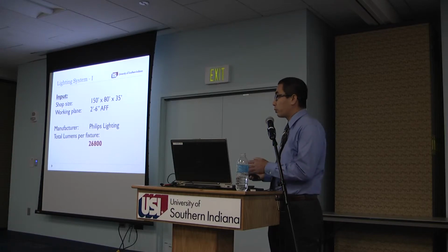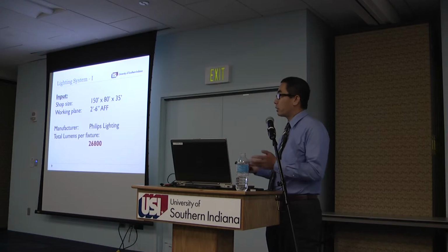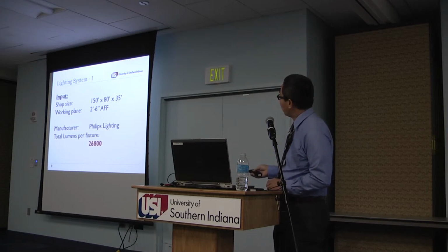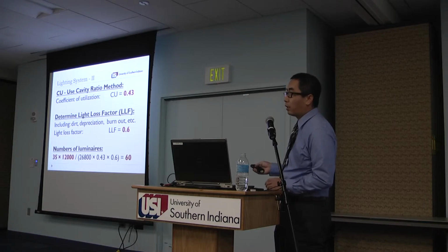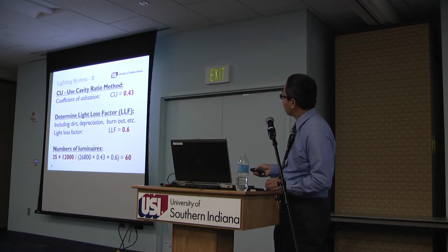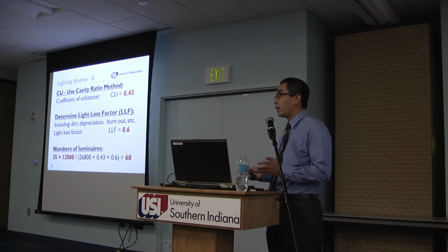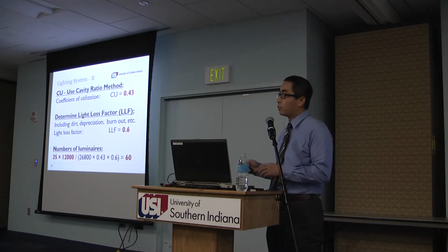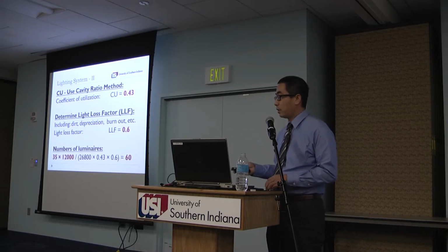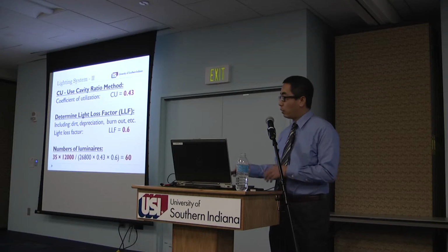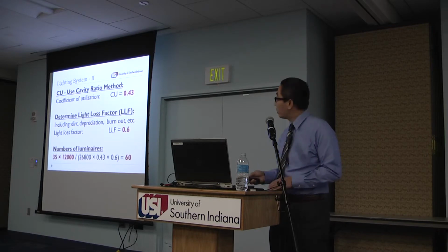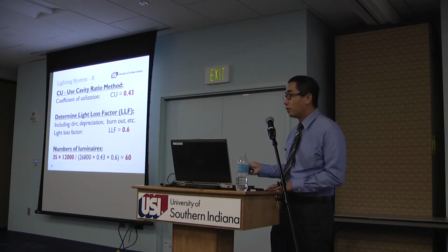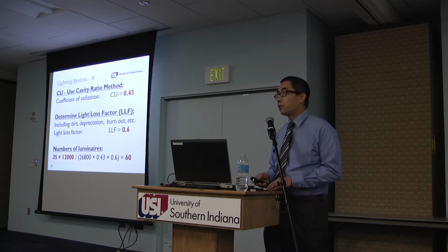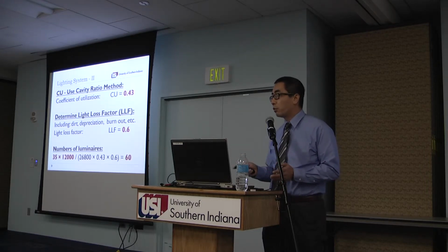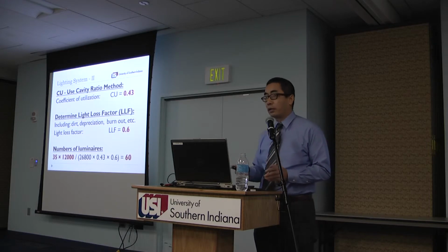But it doesn't mean that all of them are going to reach the working surface, because they're going to dissipate in the space, reflect somewhere. So we have applied some knockdown factors to get the actual lighting we need. The first one is called the coefficient of utilization. Basically, they divide the whole building into three spaces: the space above the lighting, the space between the lighting and the working surface, and the space below the working surface. Based on that ratio, you can find out the coefficient of utilization. For this one, we have 43%. So that means of the light coming out of this lighting fixture, only 43% reaches the working surface. That's the one you need to use.